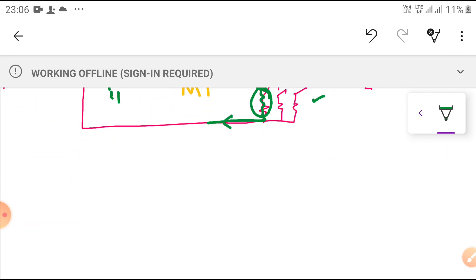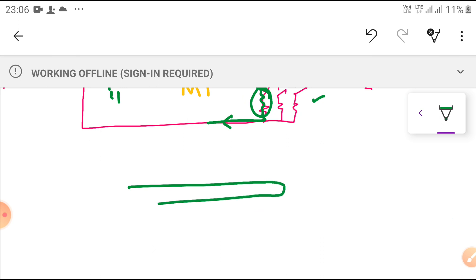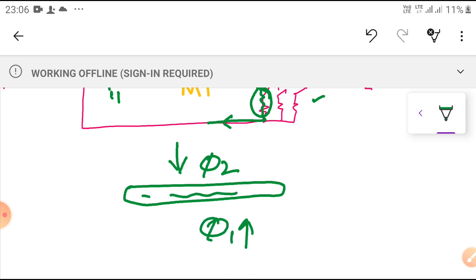The aluminum disc is a conductor. The flux phi 2 comes in this direction and phi 1 in this direction, and they link with the aluminum disc. These fluxes are changing with time — they are AC fluxes. Due to this, eddy voltage E2 is produced from phi 2, and E1 from phi 1 — eddy currents are produced in the aluminum disc.